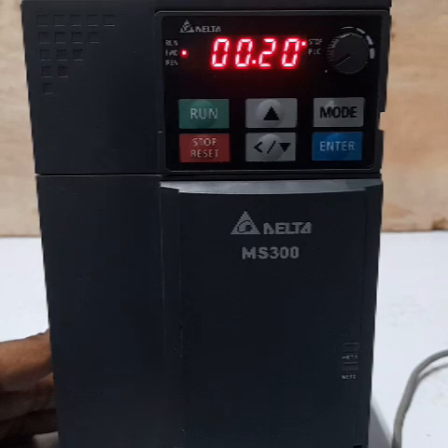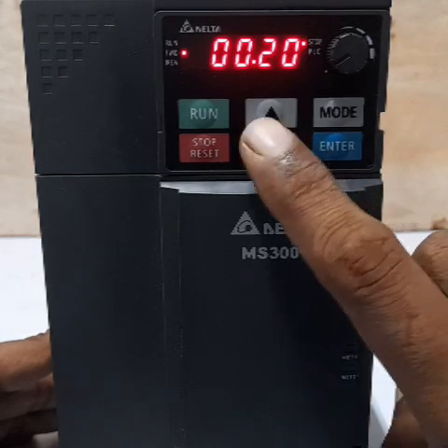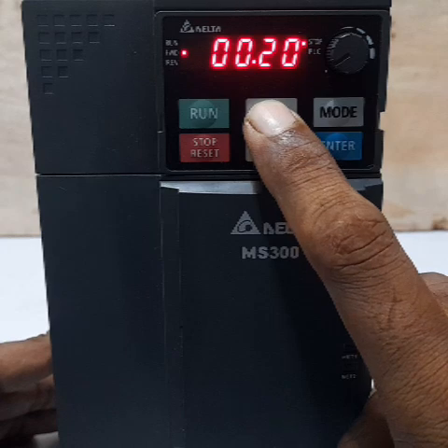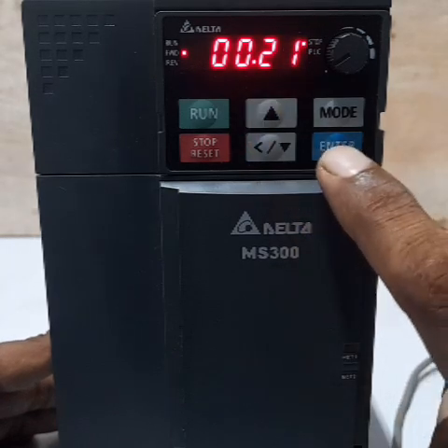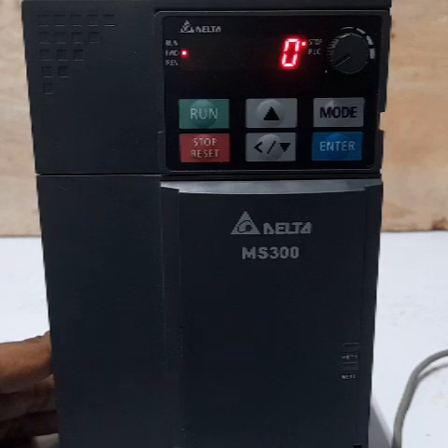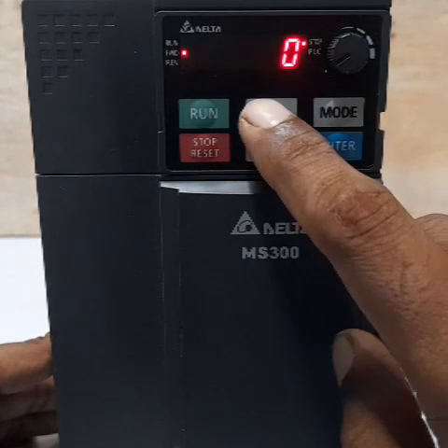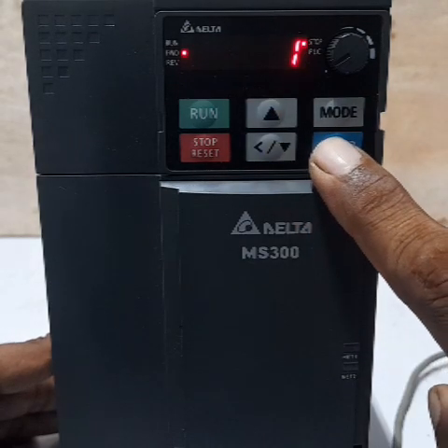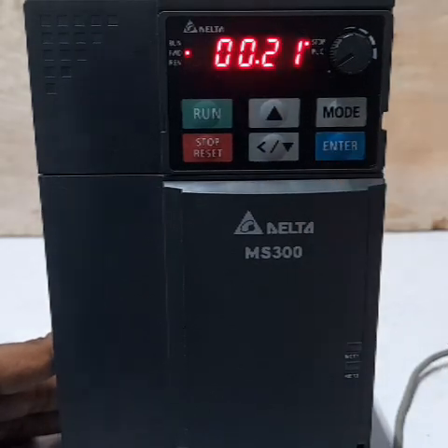Next is the operation command, parameter 00-21. Change to 1 and press Enter. The default 0 is digital keyboard run command. Our need is 1 — external run command — so the external on/off push button will be used. Press Enter.